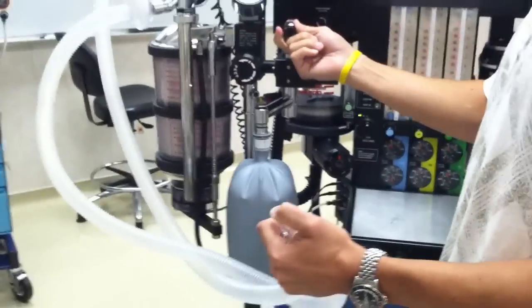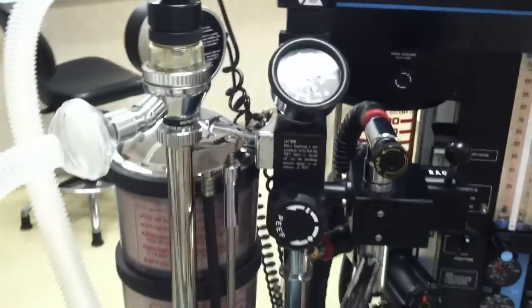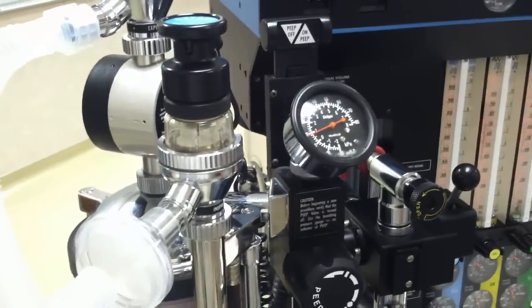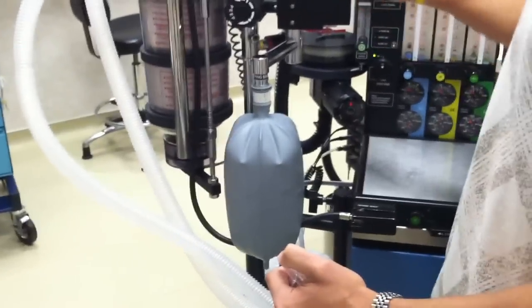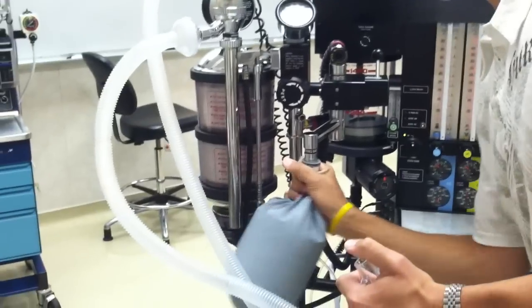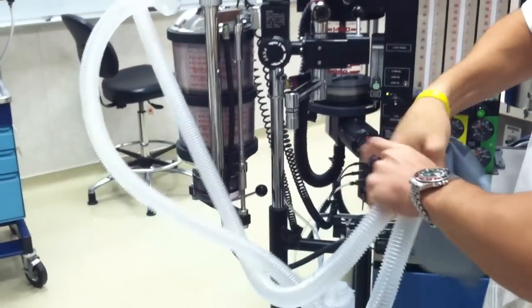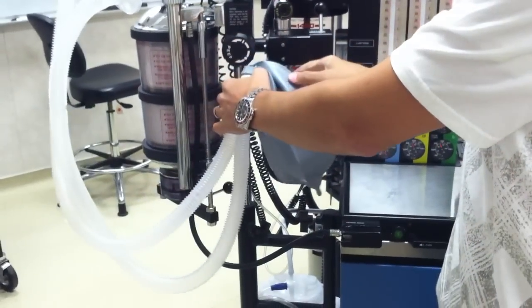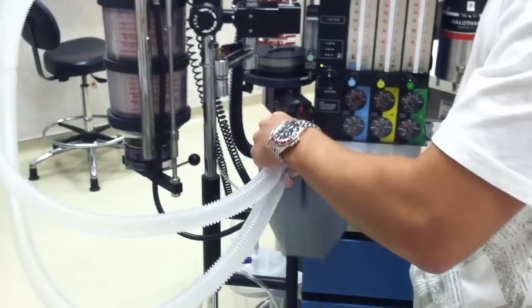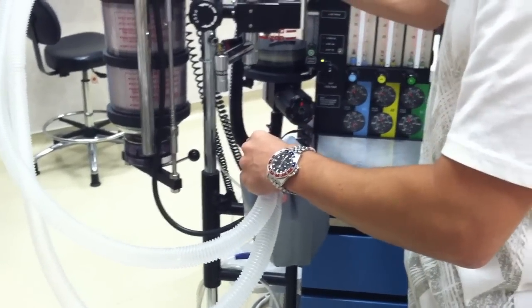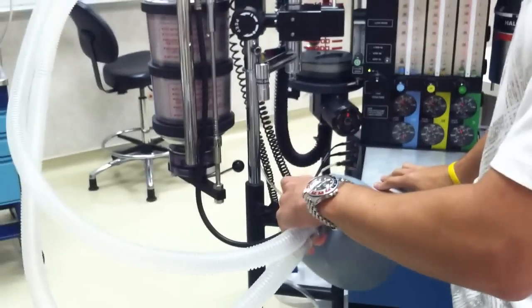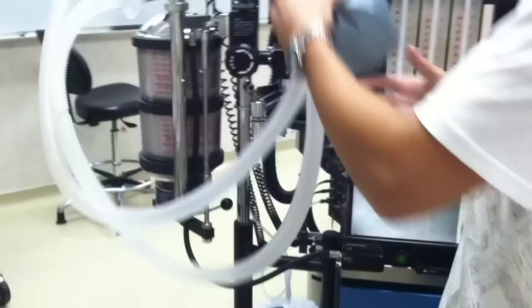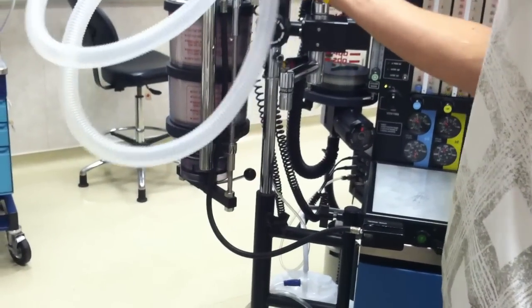Now with the APL valve all the way open, we're going to push O2 flush. Make sure that it does not go over 10 centimeters of H2O, which it doesn't. So we're good here. Now we're going to put it in vent mode. To do that, you flip the switch, turn it on, and move your bag over here. So we're good there. We're going to go ahead and fill up our bellows. That gives a little bit more. There we go. So we just let that sit for a minute while you do your check.